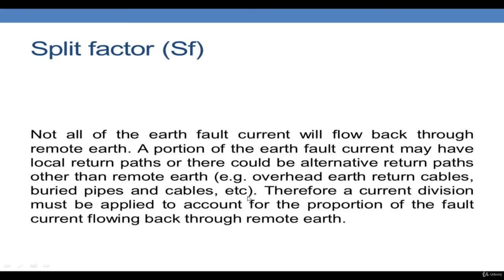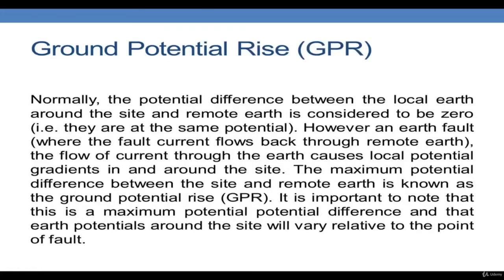So we are actually over engineering this so that we do not have any problems regarding our safety. Another factor is that the split factor is very difficult to calculate, and there are other regulations put forward by IEEE in order to calculate the split factor. So in our case and in many cases we use 100% as the split factor.